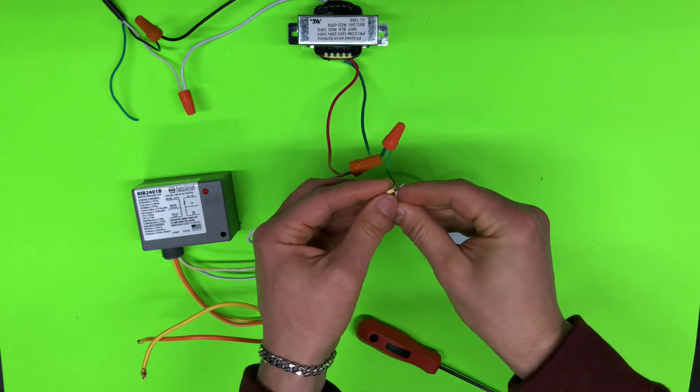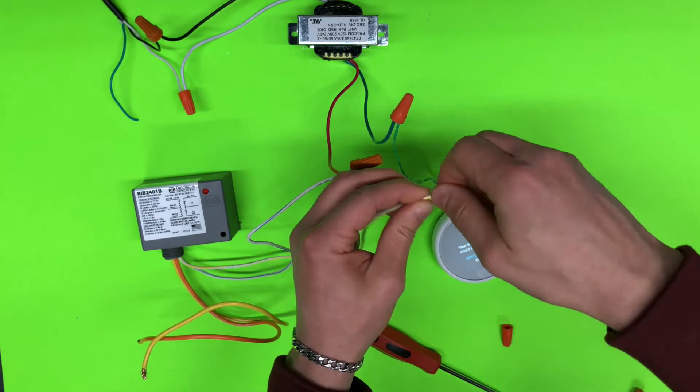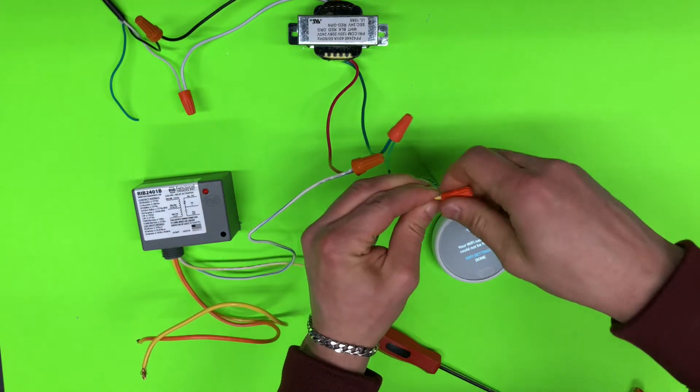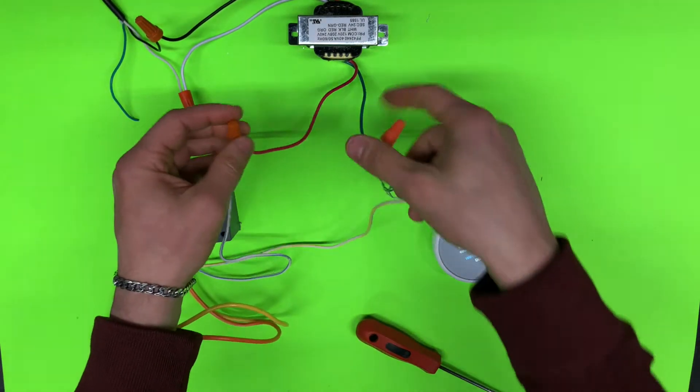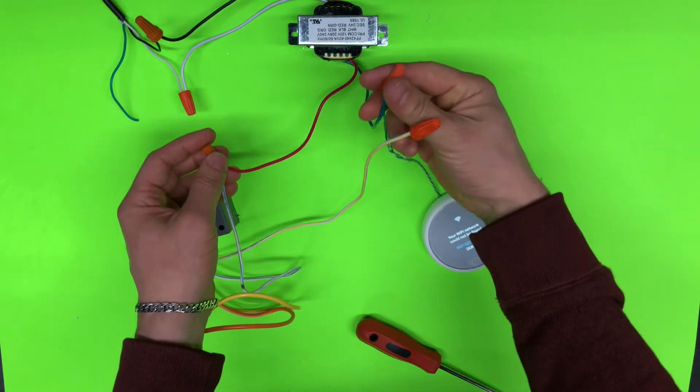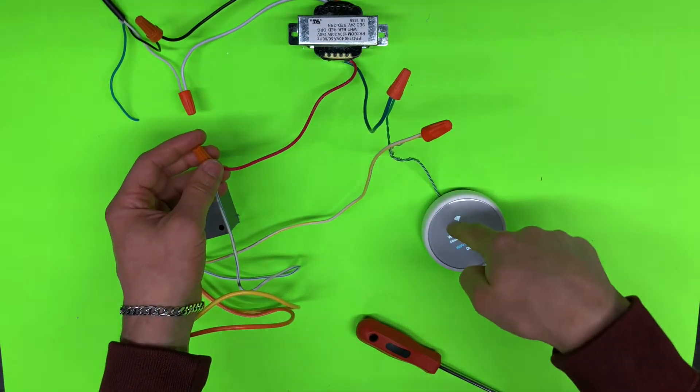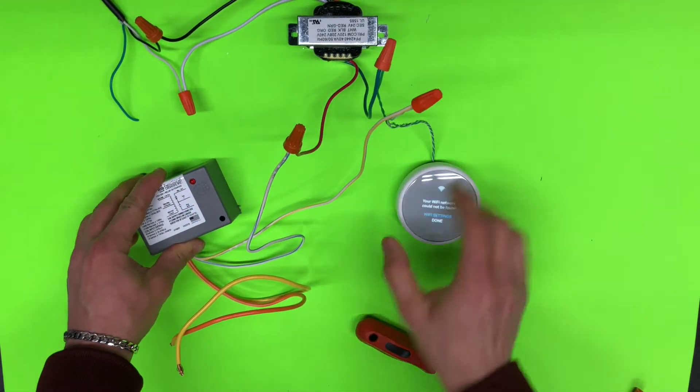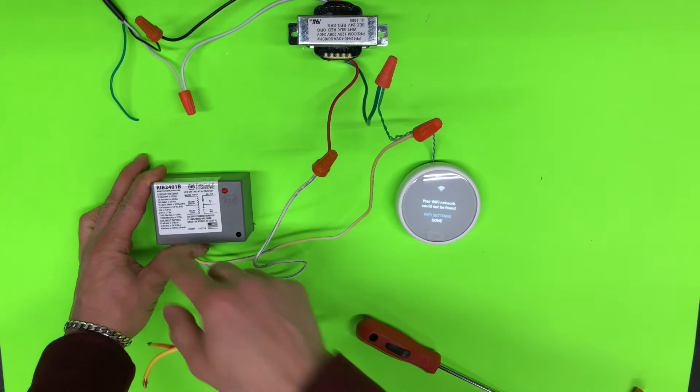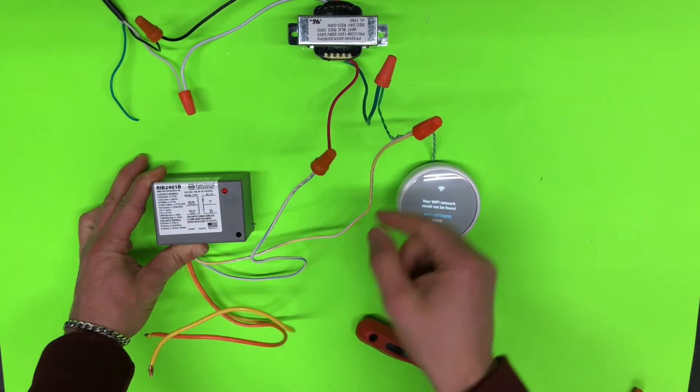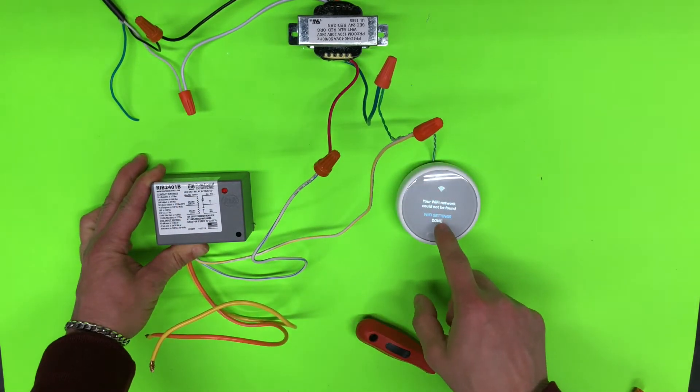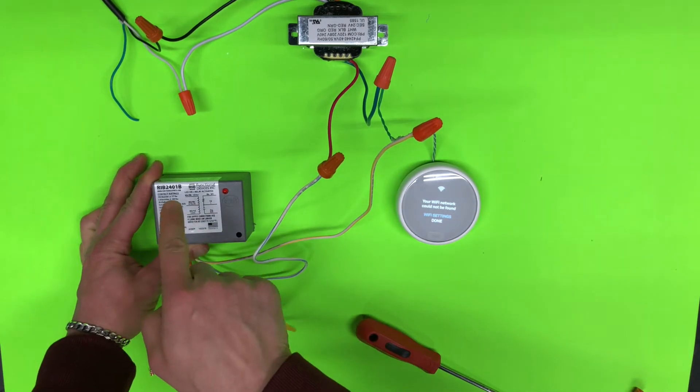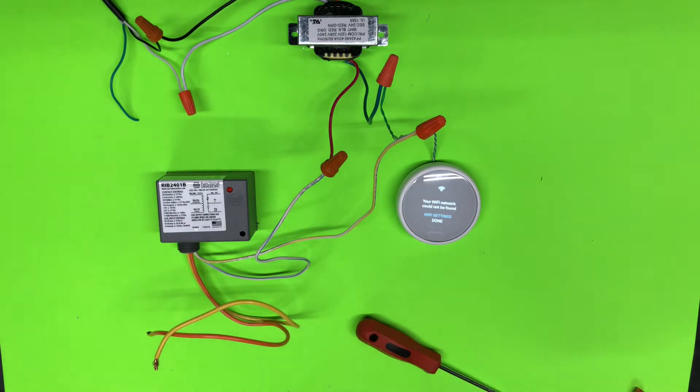So right now our thermostat is going to be connected in series. So that means here's our transformer, one power is going to thermostat and second power from transformer is going to relay. So thermostat will go through the coil and power itself. And when we need to send power, it's going to short these contacts and energize our relay. So let's turn power on and see how it works.